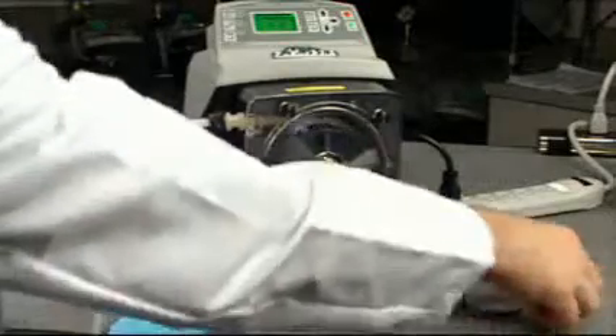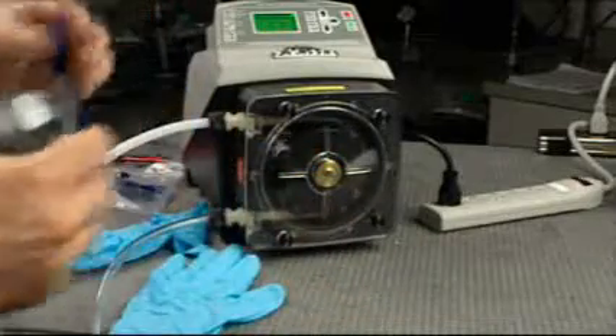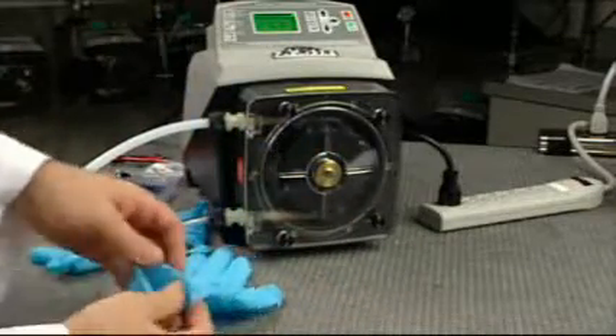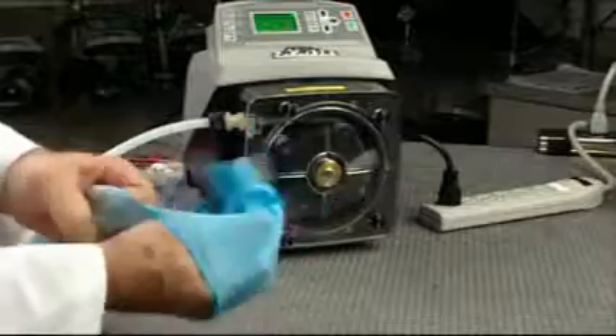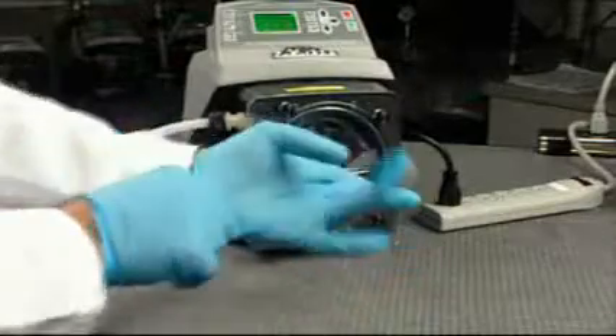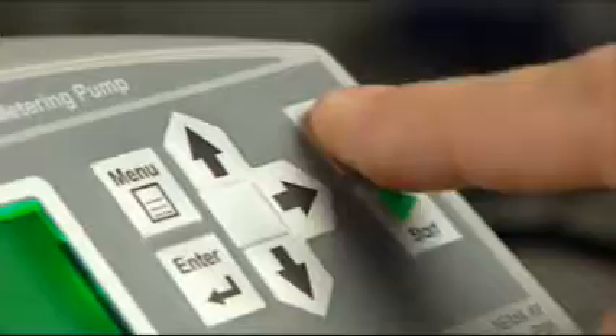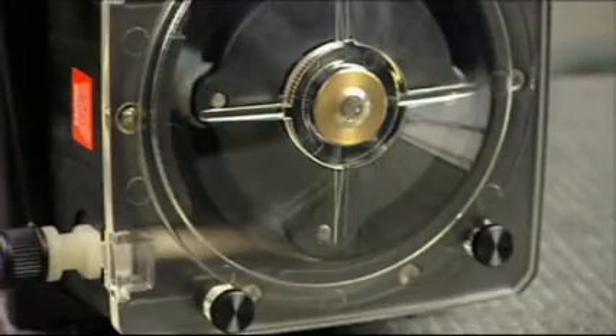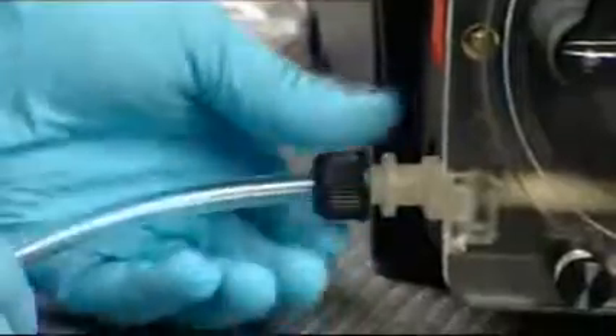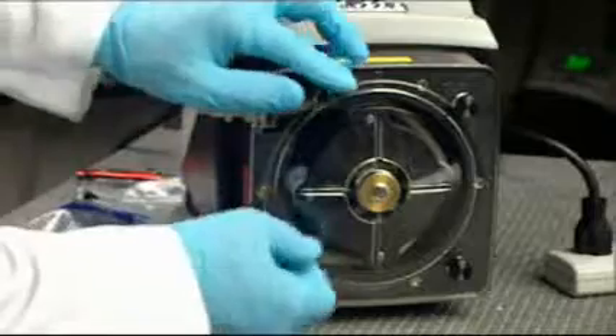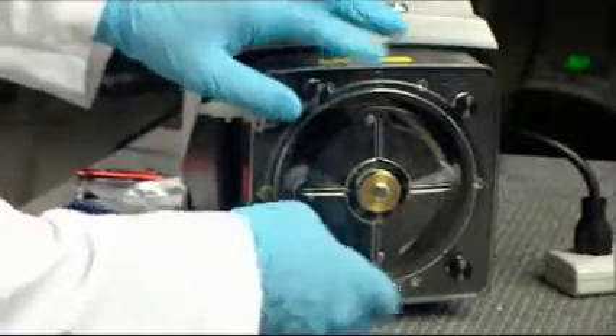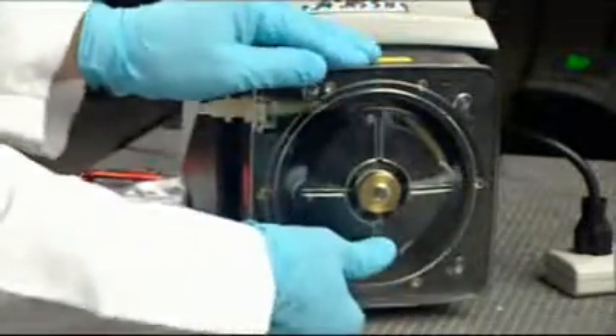Use caution when disconnecting the tubing. It may be under high pressure. Note that protective clothing and safety glasses should be worn while servicing the pump. Press the stop button to stop the pump. Disconnect the suction and discharge tubing from the pump tube. Remove the 4 thumb screws from the pump head cover. Remove the cover.